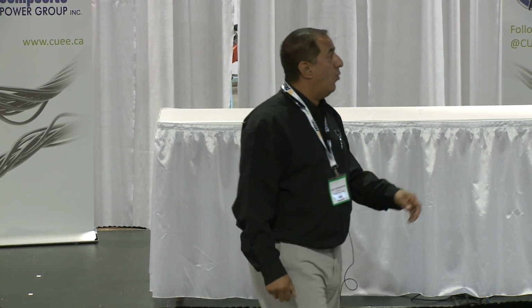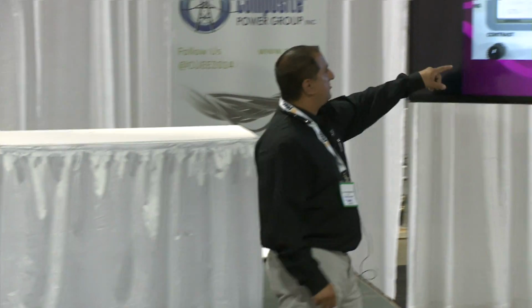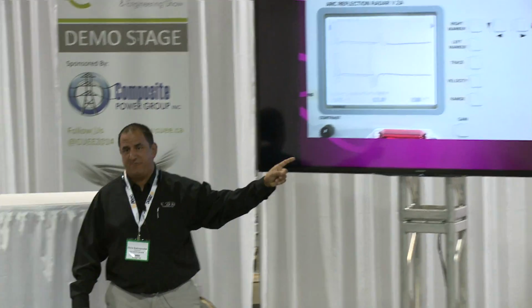Now, what you're going to do is push the start button. And when you push that start button, you're going to charge that capacitor up. You can set the voltage to anywhere between 3 all the way up to 25 kV. On an isolated piece of cable, one of two things is going to happen. It's either going to hold voltage if my cable's good, or it's going to discharge if there's a fault. Once it finds the fault, that's what you're going to see. The machine tells you, right marker at fault. So now we had an 800-foot piece of cable, and now we've gone to 678 feet. And that's where our fault is going to be.